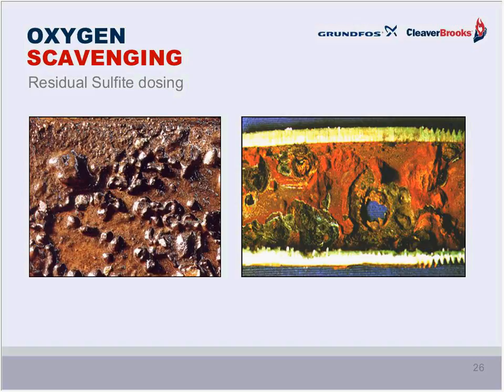And as far as the boiler water is concerned, we need to inject sulfite to eliminate any remaining oxygen following preheating, and to attack any oxygen which may have entered the boiler due to, let's say, leaks or possibly a vacuum. The sulfite, it should be noted, turns to sulfate within the boiler, which, as you will recall, is a total dissolved solid and needs to be removed through continuous blowdown.